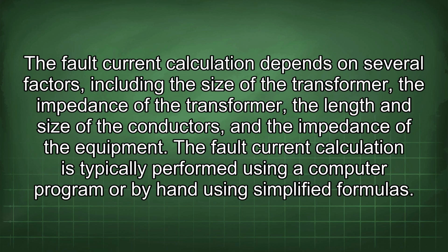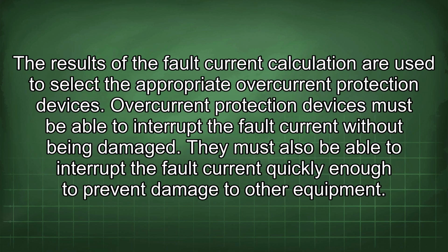The fault current calculation depends on several factors, including the size of the transformer, the impedance of the transformer, the length and size of the conductors, and the impedance of the equipment. The fault current calculation is typically performed using a computer program or by hand using simplified formulas. The results of the fault current calculation are used to select the appropriate overcurrent protection devices.